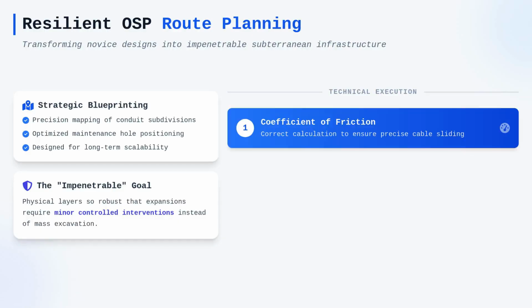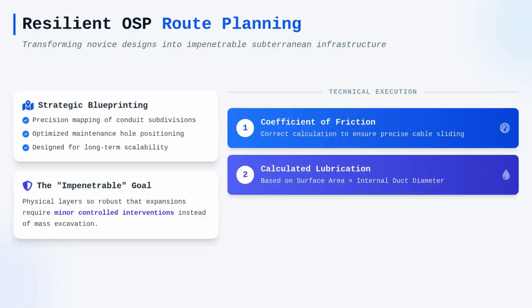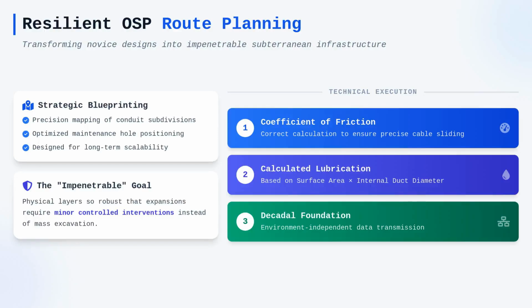By calculating the coefficient of friction correctly and choosing the appropriate lubricants, you ensure that the cable slides through the conduit segments according to the design plan. Remember that the lubricant volume is not a guessing game. It is a calculated variable based on the total surface area of the cable and the internal diameter of the duct, aimed at reducing the dynamic friction to safe levels. Through these systematic calculations, you build a foundation that supports data transmission for decades to come, independent of the external environment.